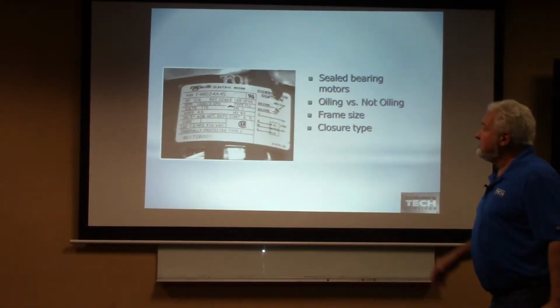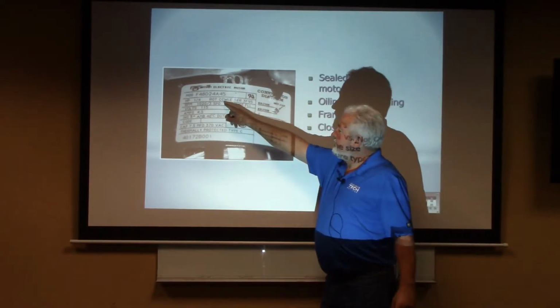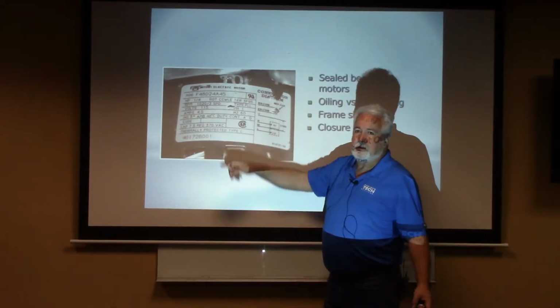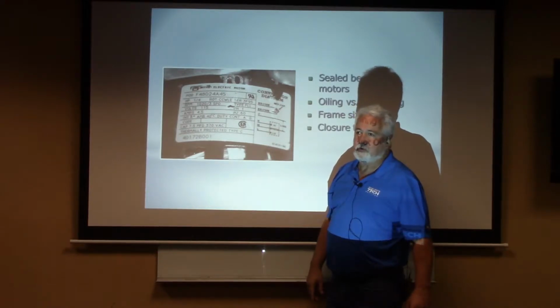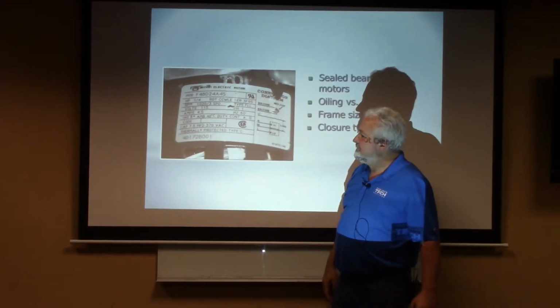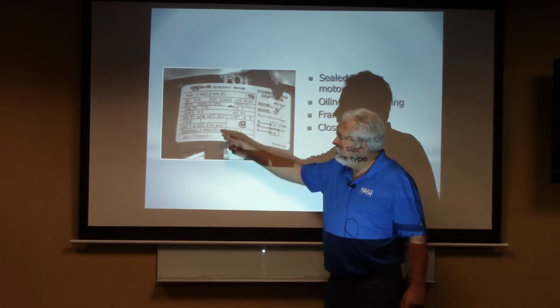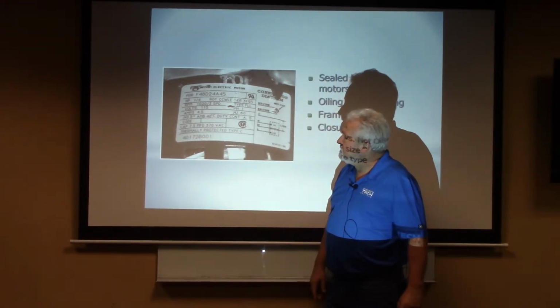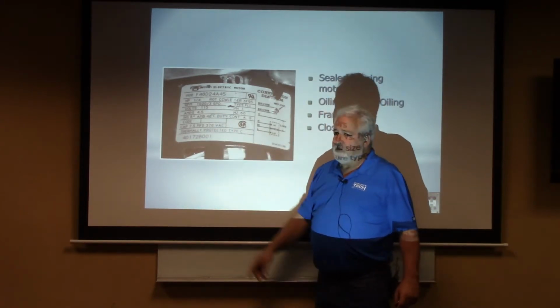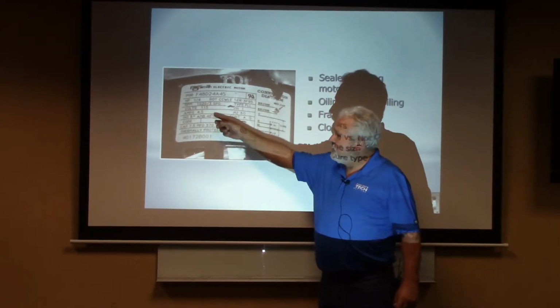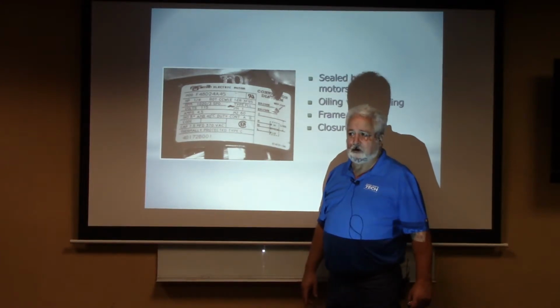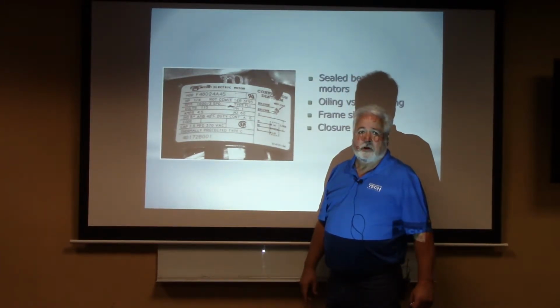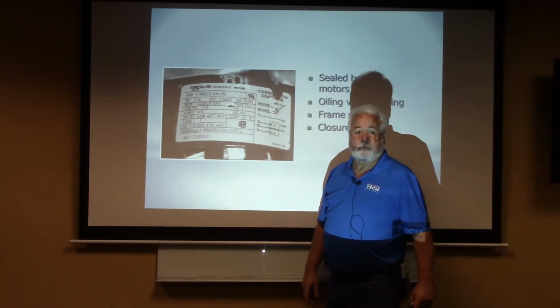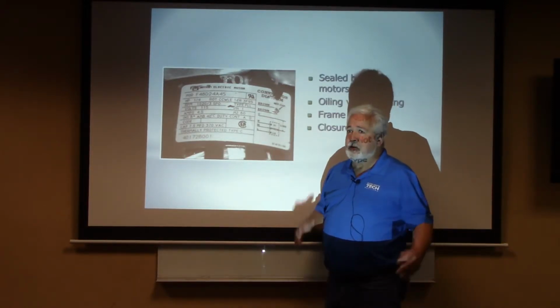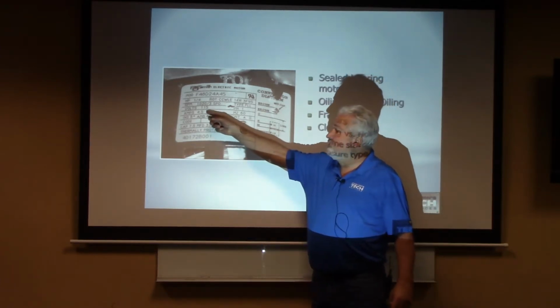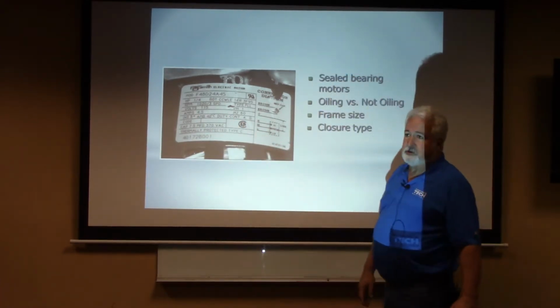All right, so you'll get that information right here. What is this? Counterclockwise lead end. They're telling you right there on that motor, and typically that's where we're going to see those set up. Look, it's got a capacitor, 7.5, 370 volts AC. There's my amperage. If you're questioning horsepower between motors, your amperage is probably going to be your best bet. Some of your OEM motors are going to bump up the amperage to drop the horsepower, so you have to buy their OEM motor. If you're in doubt on the horsepower, check your amperage. That's going to be your best bet.